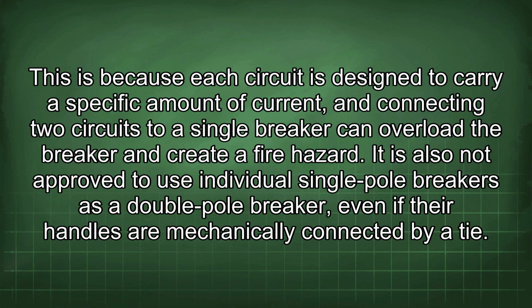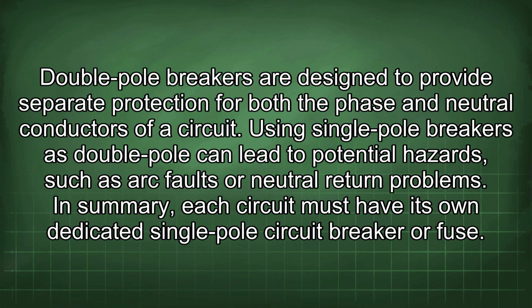It is also not approved to use individual single-pole breakers as a double-pole breaker, even if their handles are mechanically connected by a tie. Double-pole breakers are designed to provide separate protection for both the phase and neutral conductors of a circuit. Using single-pole breakers as double-pole can lead to potential hazards such as arc faults or neutral return problems. In summary, each circuit must have its own dedicated single-pole circuit breaker or fuse.